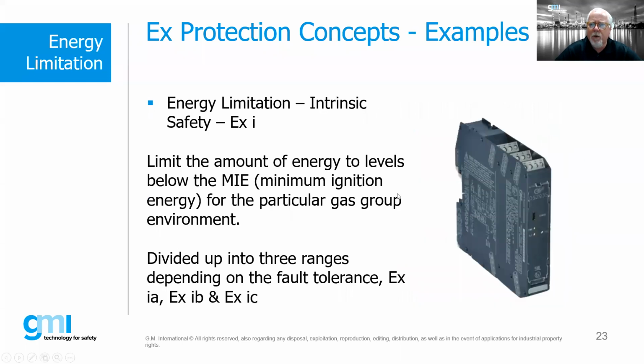So let's continue on. So energy limitation, intrinsic safety, is considered to be EXI. This limits the amount of energy to levels below the minimum ignition energy for the particular gas group environment. And within barriers, we actually have three ranges, if you will, based upon the fault tolerance. So if you've been part of some of our other webinars on the fundamentals of intrinsic safety, an EXIA barrier, in effect, will have three Zener diodes. Two of them are for redundant applications. The difference between an EXIA barrier and an EXIB barrier is basically that extra Zener diode, if you will. So we have a little bit higher level of safety. So therefore, EXIA is suitable for zone 0 applications.